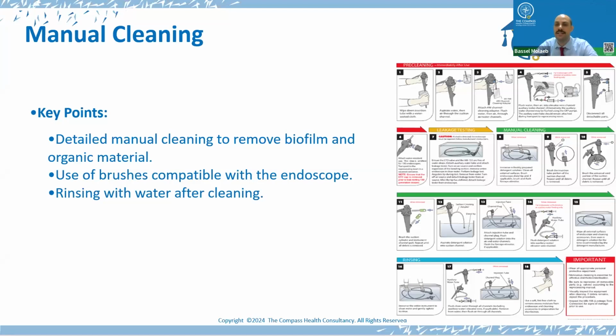You should disconnect and disassemble endoscope components like the suction valves as far as possible and completely immerse the scope and the components in the detergent. And definitely IFUs should be followed for the proper dilution, the temperature, and the contact time. And in that manner, the scope should be meticulously cleaned with the entire endoscope having its accessories, the valves, the channels, the connectors, and all the detachable parts according to the IFUs using specific and convenient brushes and items for cleaning.